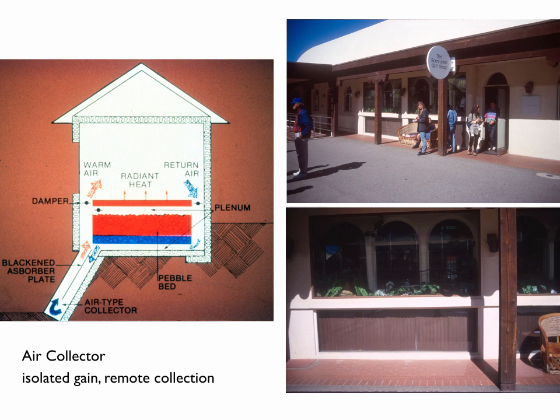And the main point here is that you always are using some type of engineered, designed solar heating collector, which is not necessarily part of the building structure, but could be, right? So in that diagram on the left-hand side, the air collector is down low, right? And it's completely separate, really, from the space and also separate from the storage. So the sun comes in, comes through a glass plate, hits a metal collector, right? That metal collector is an absorber, right?